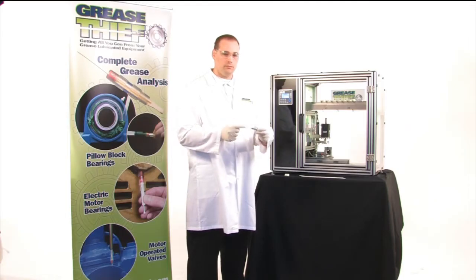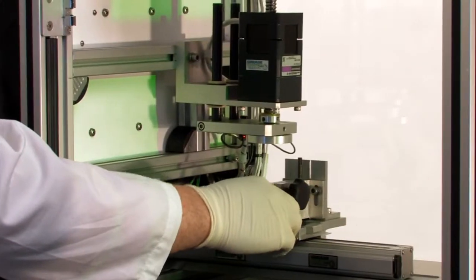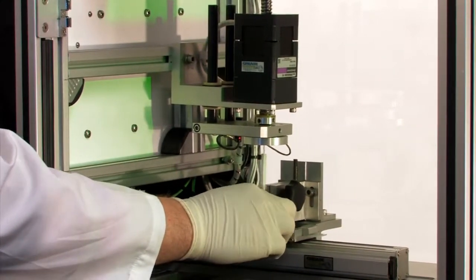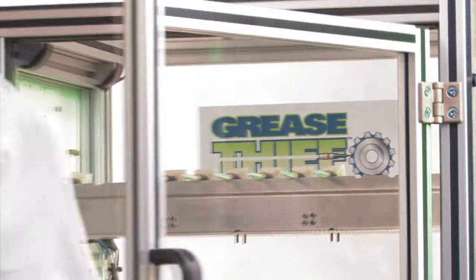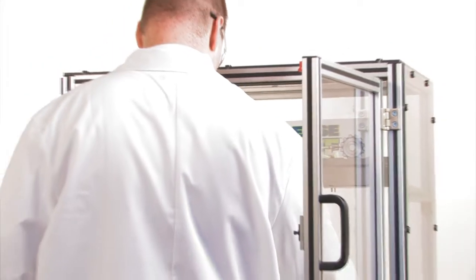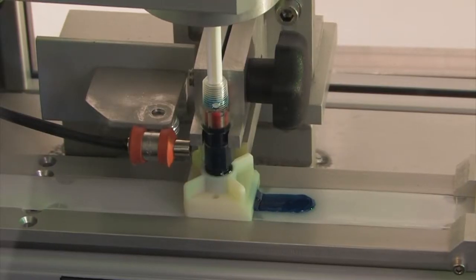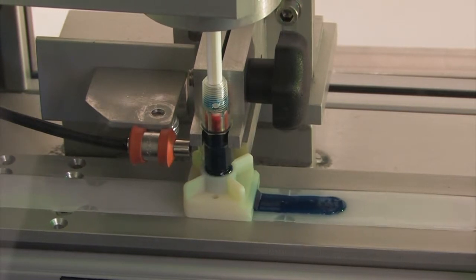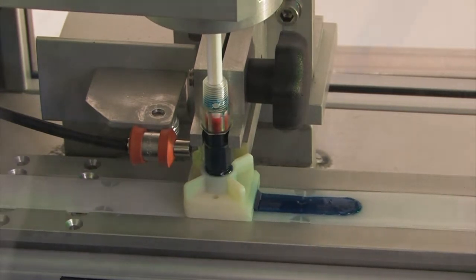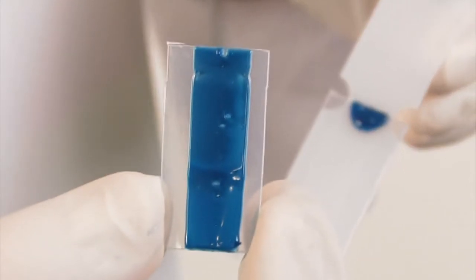How can significant testing be done on one gram of grease? The answer lies in the efficient Grease Thief analyzer design and the patented technology behind the Grease Thief extrusion die — an innovative device that both evaluates a grease's change in consistency and prepares a thin film of grease for analysis. This streamlined analysis method drives overall sample processing costs down and enables the most cost-effective analysis options.